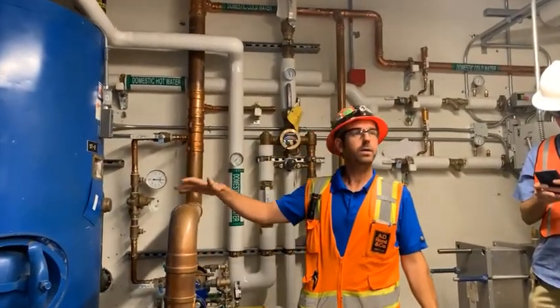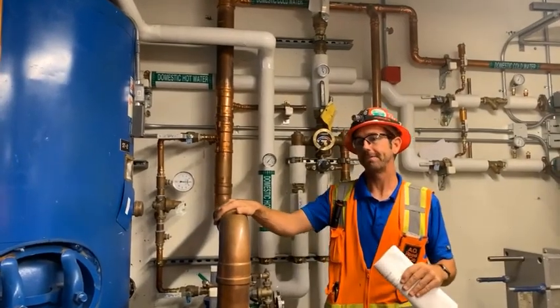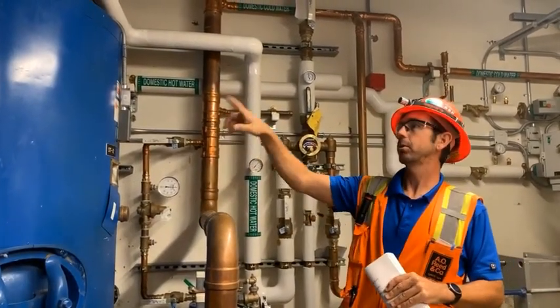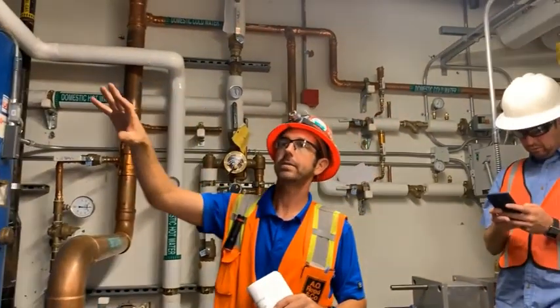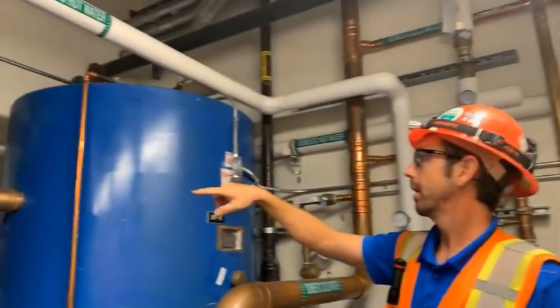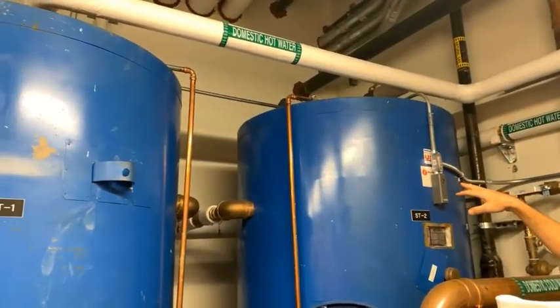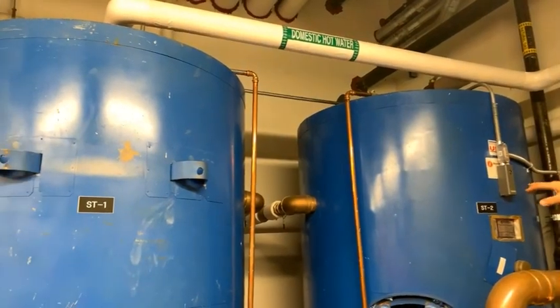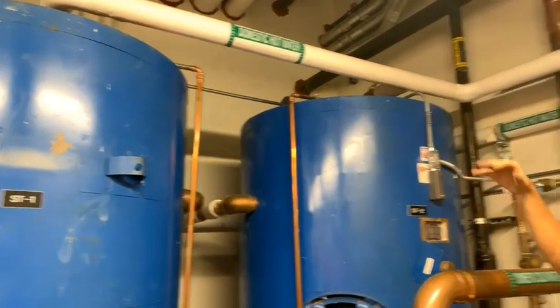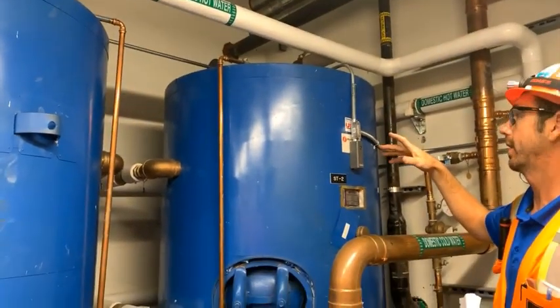All right, we're still here. We're still back in the mechanical room, building A, first floor. We have 2 storage tanks. So these are domestic hot water storage tanks. They're storing water at 140 degrees. Anytime you store water in a tank, we gotta be at 140 for Legionella.